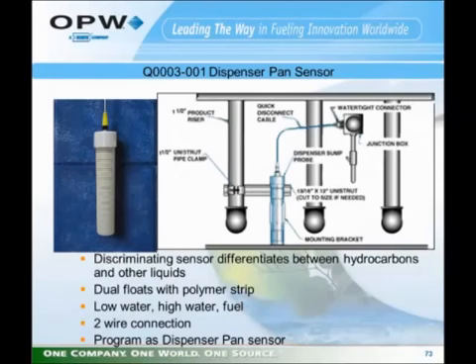The Q0003-001 is a dispenser pan interface sensor. It is designed to be installed in a pan underneath a fuel dispenser. It will discriminate. It will tell you whether you have fuel in that space or water or both. It has two floats for low and high level detection, and it has a polymer strip to detect hydrocarbons that may be present. So we can issue a low water alarm, a high water alarm, a fuel alarm, a low fuel alarm, and a high fuel alarm. It uses a two-wire connection back to the leak sensor interface module, and in the unit it is programmed as a dispenser pan sensor.